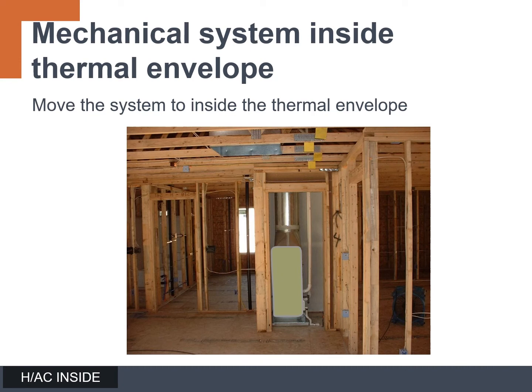Let's talk about moving that mechanical system inside the thermal envelope. This could involve designing a space, maybe converting a closet on the second floor, or getting creative with some other design options. The biggest benefit to this strategy involves making the smallest amount of changes to the thermal envelope, as well as providing easy access for homeowners and technicians in the future. In this variation, the return duct is still in the attic — it looks like about five or six feet down the hallway from where the furnace is, probably about a 10-foot loop of duct, which qualifies as that exception and still avoids too much sound transfer.